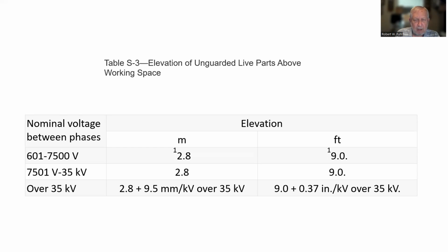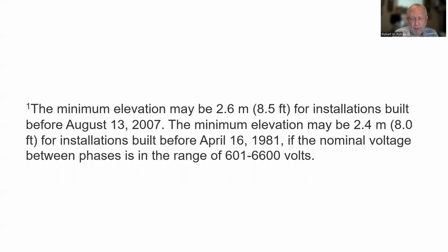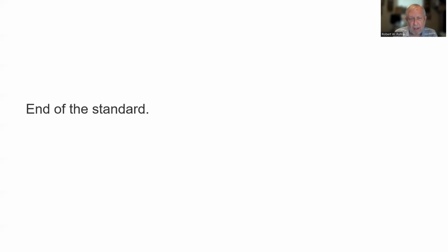That's table 3, elevation of unguarded live parts above the working space. This is the means you get them up. You're basically providing engineering control of moving them out, away from people. Minimum elevation may be 8.5 feet for installations built before August 2007. Minimum elevation may be 8 feet for installations built before April 16, 1981, if the nominal voltage between phases is in the range of 601 to 6600 volts. And that's the end of that standard.